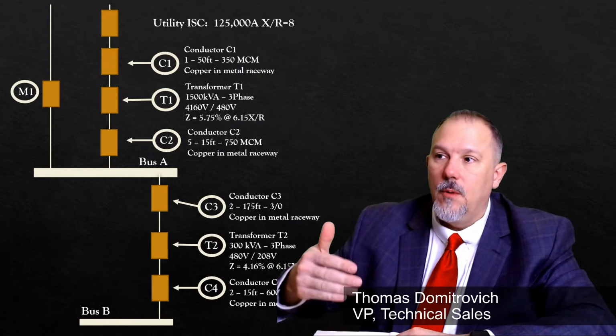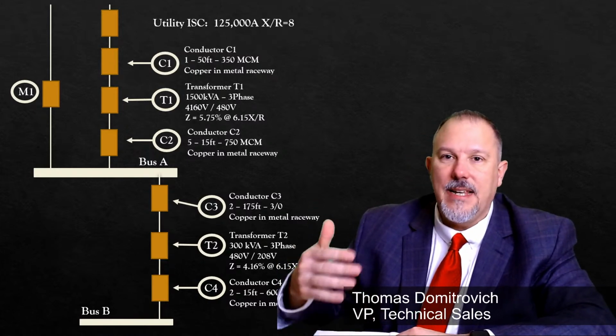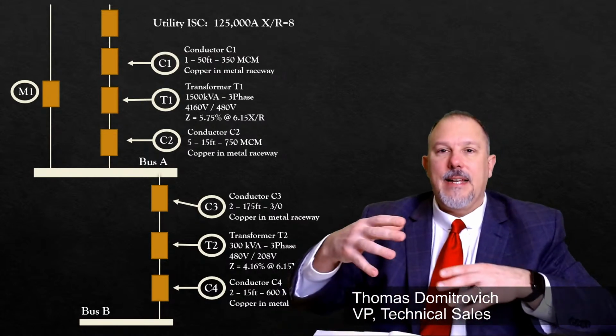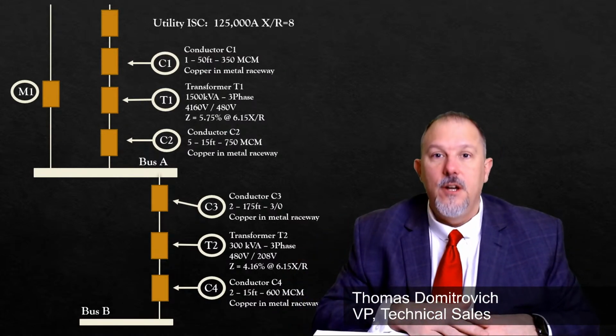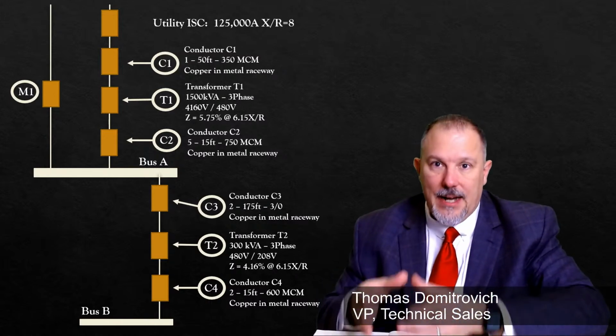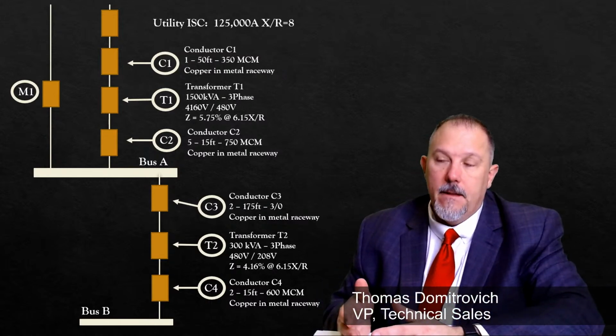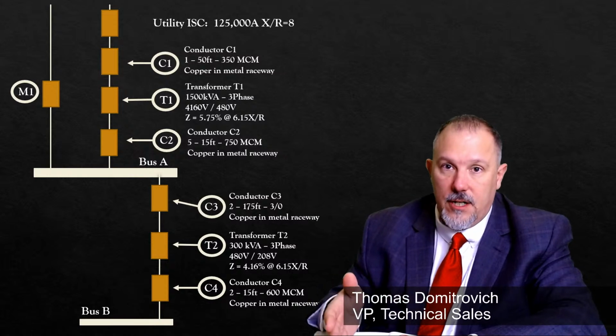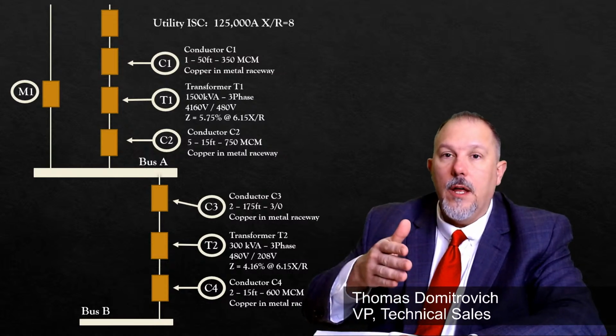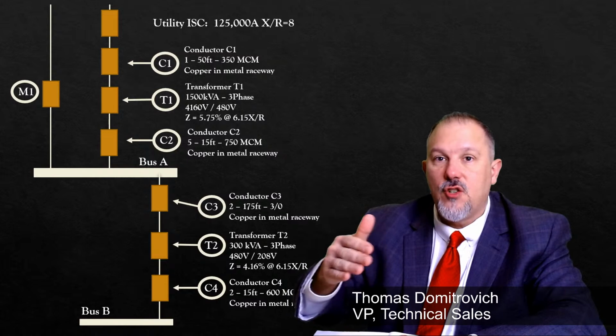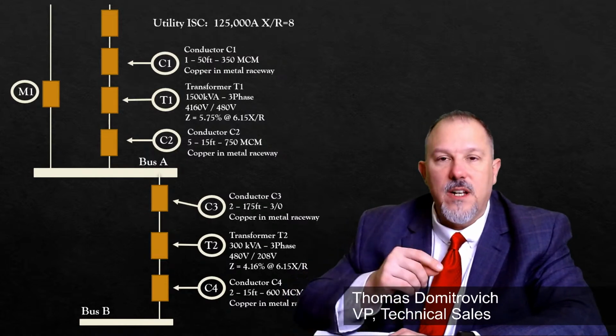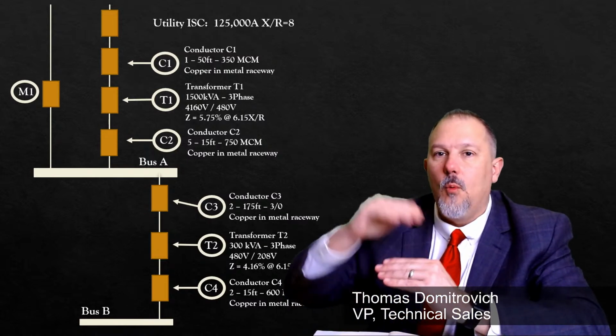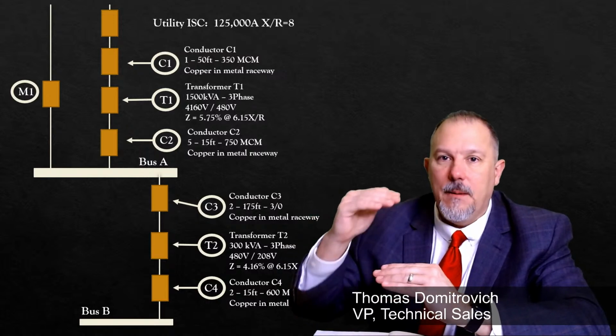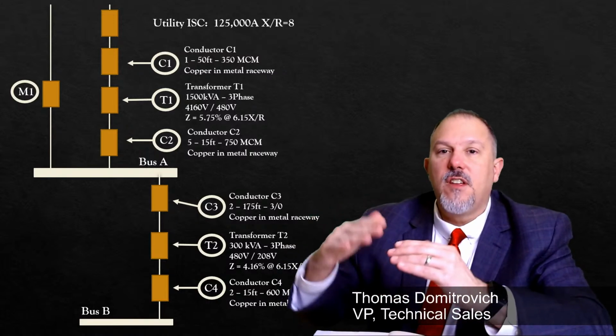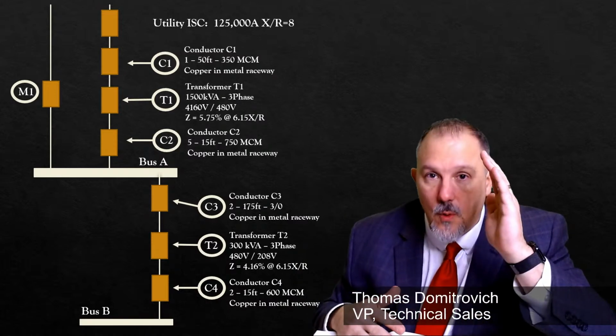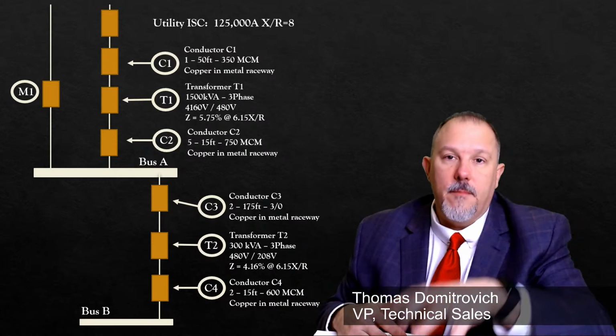Why would you multiply a transformer impedance by 1.1 to get a lower fault current value? For incident energy analyses. When I'm looking at incident energy, I'm going to increase the impedances of my transformer. Assume that my transformer is worst case at 1.1, the higher impedance value. That'll give me a lower fault current, which could put me into a longer clearing time on my circuit breakers.